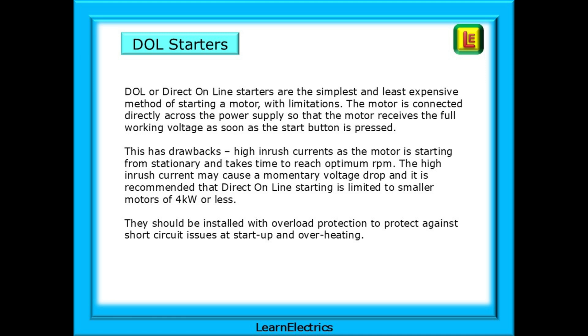DOL or direct online starters are the simplest and least expensive method of starting a motor, with limitations. The motor is connected directly across the power supply so that the motor receives the full working voltage as soon as the start button is pressed. This has drawbacks: high inrush currents as the motor is starting from stationary and takes time to reach optimum RPM. The high inrush current may cause a momentary voltage drop on the supply, and it is recommended that direct online starting is limited to smaller motors of 4kW or less. This should be installed with overload protection to protect against short circuit issues at startup and overheating.